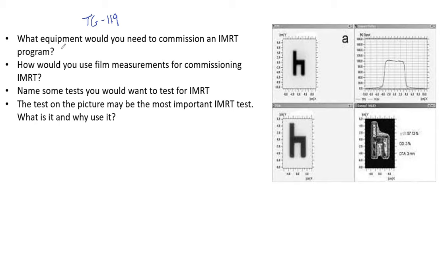You also want a chamber that is smaller than a Farmer chamber. Farmer chambers are quite large in the chamber world, so you would want a chamber around 0.125 cc ideally. A CC13 or something similar is a perfect type of chamber. You can use the water phantom with a chamber, but you can also use film.